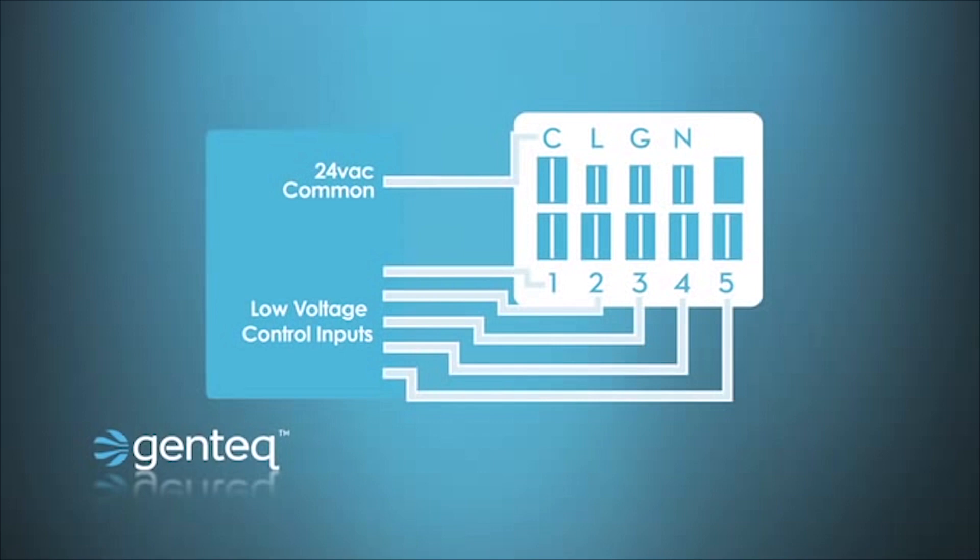Now these taps are also programmed for multi-state inputs, and what that means is you can turn on more than one tap at a time without damaging the motor. In other words, you can energize tap one and tap two at the same time, the motor will simply do whatever stored in tap two. You can turn on one, two, and three, it'll do what's in three and so on and so forth.